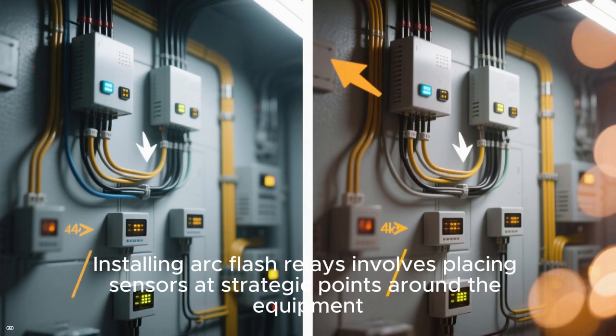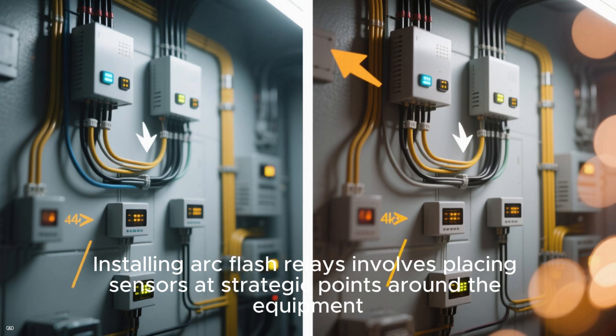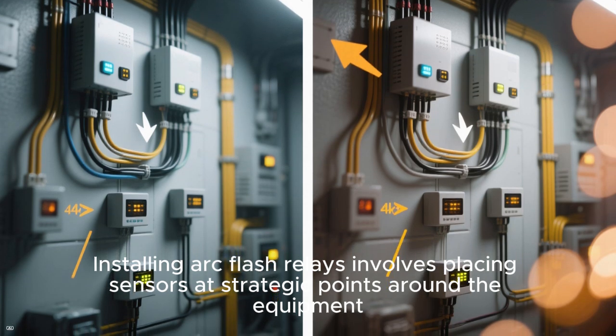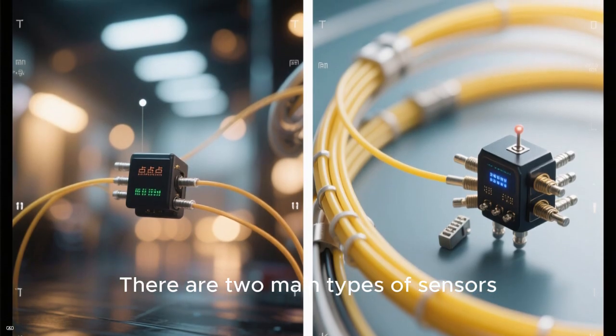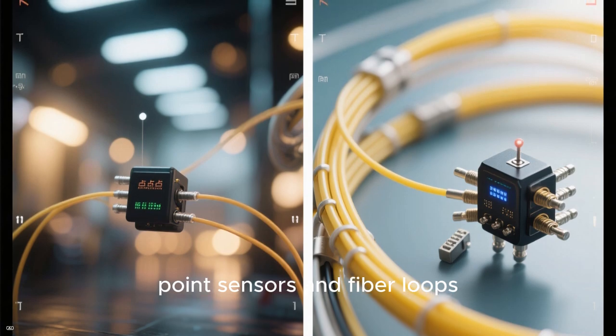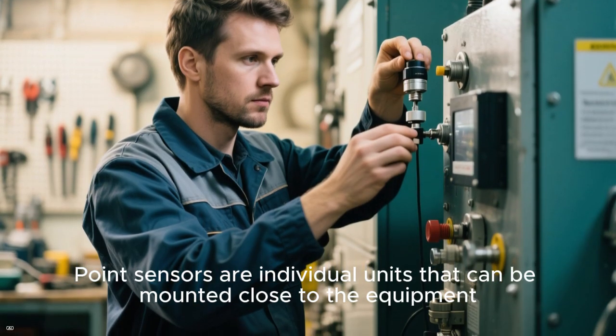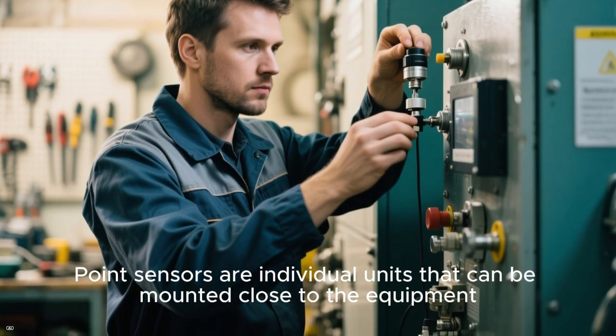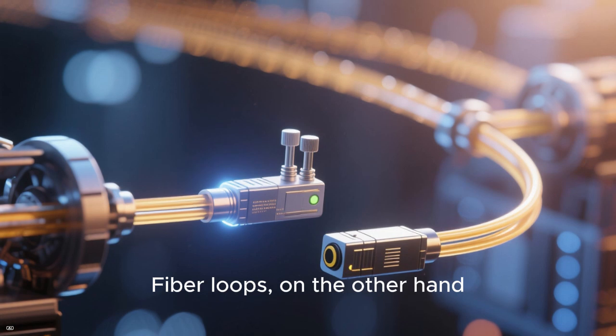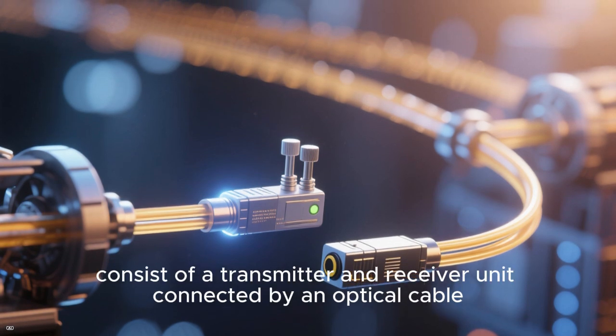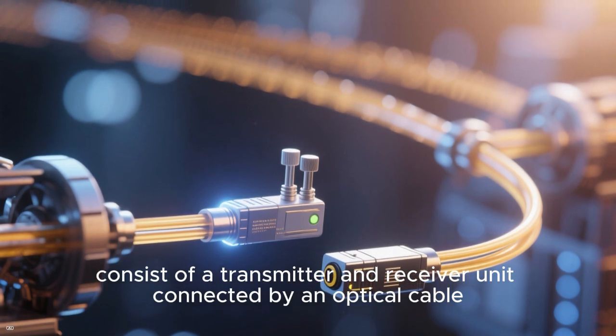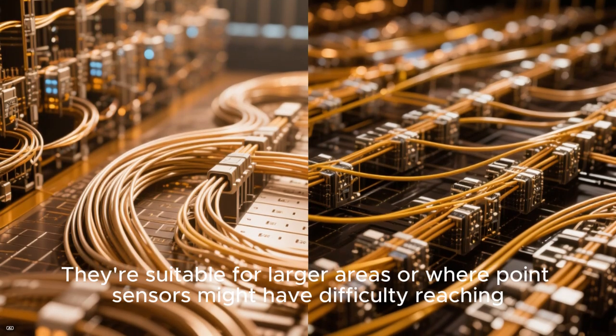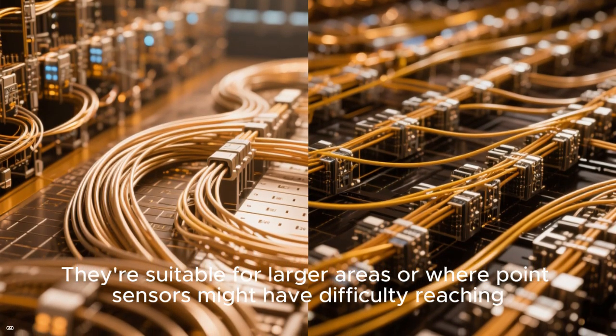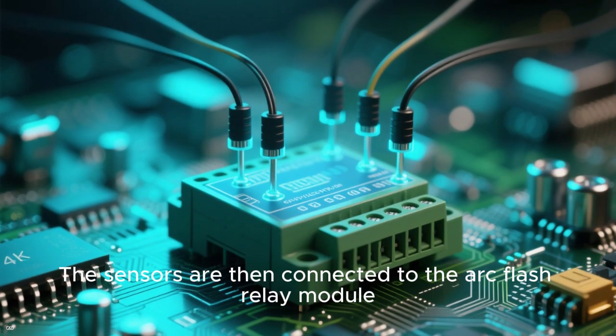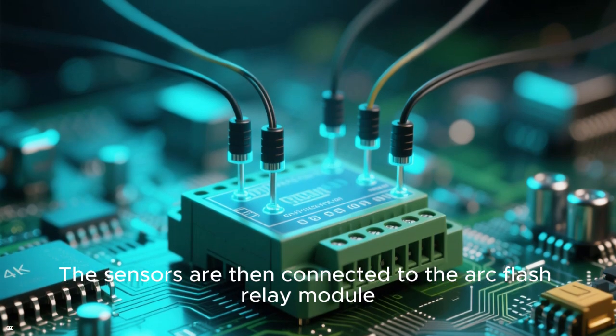Installing arc flash relays involves placing sensors at strategic points around the equipment. There are two main types of sensors: point sensors and fiber loops. Point sensors are individual units that can be mounted close to the equipment. Fiber loops, on the other hand, consist of a transmitter and receiver unit connected by an optical cable. They're suitable for larger areas or where point sensors might have difficulty reaching. The sensors are then connected to the arc flash relay module.